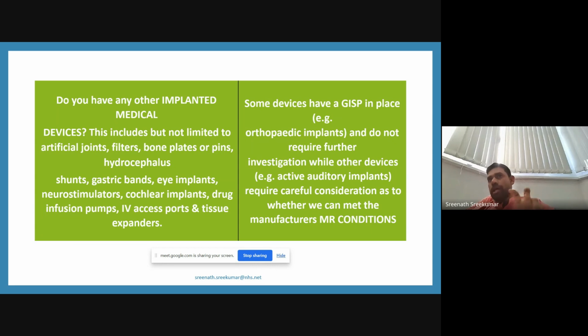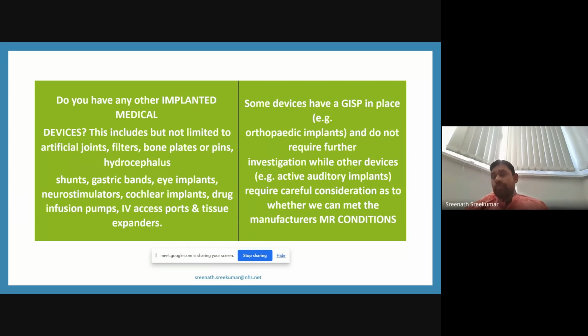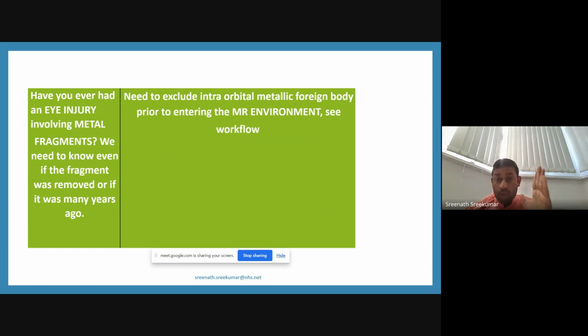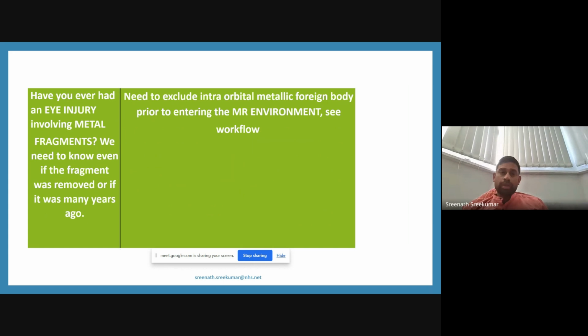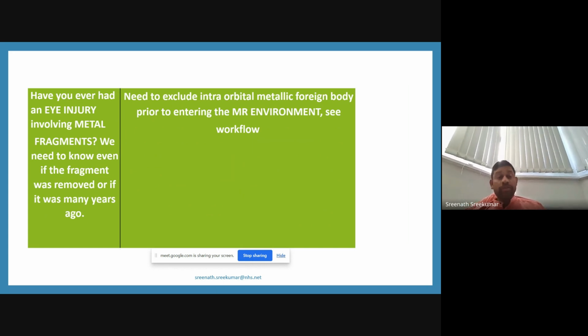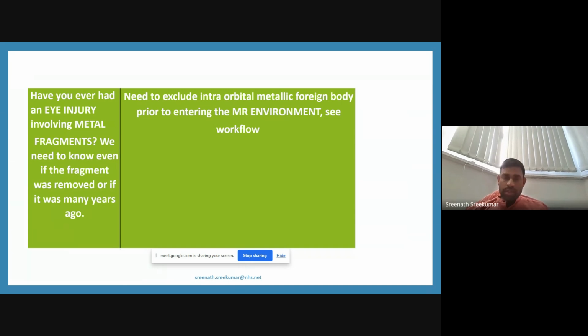And also infusion pumps. I have been seeing some infusion pumps being sent for scanning. They have guide wires inside, which are MR non-conditional equipment, and which pose a risk of burning for the patient, not a projectile risk, but burning issues. Also, cochlear implants, not every cochlear implant is safe. We have to check the safety and guidelines mentioned in the manufacturer's guideline before going for the scan. There are a lot of neurostimulators also, the same. We have to follow the things. I'm going quickly because these are long detailed documents, to keep it short for you. That's why I'm going a little bit faster. If you have any doubts, we'll discuss in the later part.